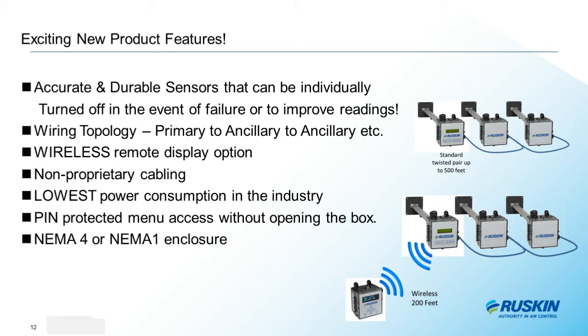The primary probe is available with or without a display. The primary probe is the interface point with the automation system and is also available as a remote primary controller, making it possible to install just the primary display and automation interface up to 500 feet away from the air measurement station's location. The wired remote display option is connected as another ancillary device, just like the ancillary probes, to the probe network. No addressing required because the remote display is hard-coded into the primary probe and will duplicate all the functions of the primary display when wired on the probe network.